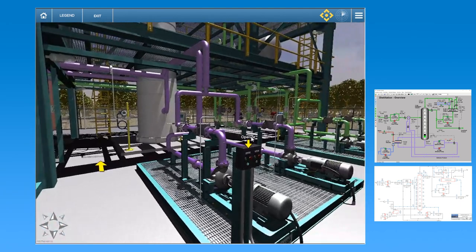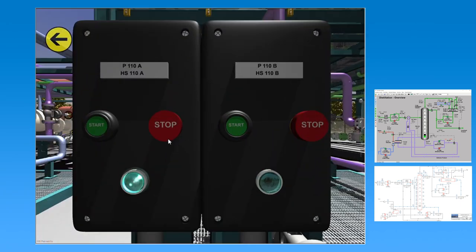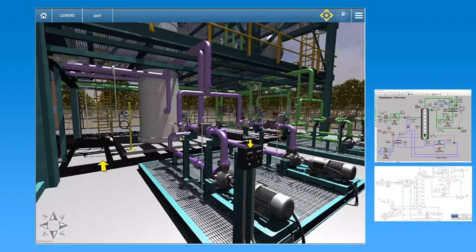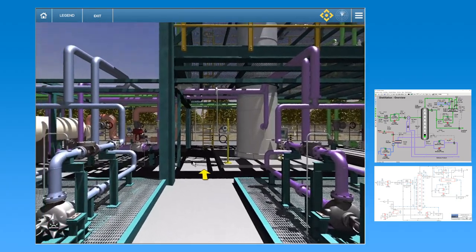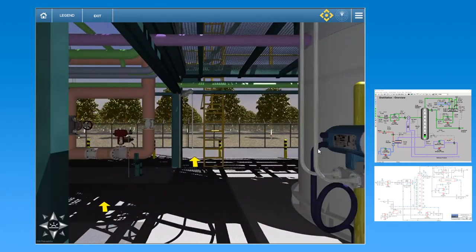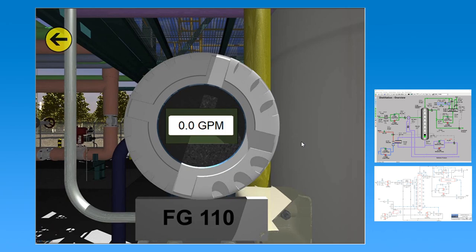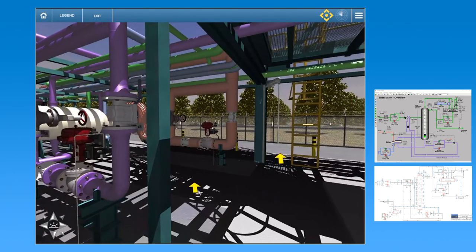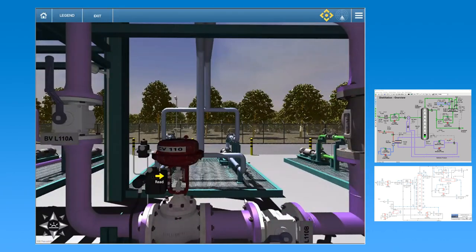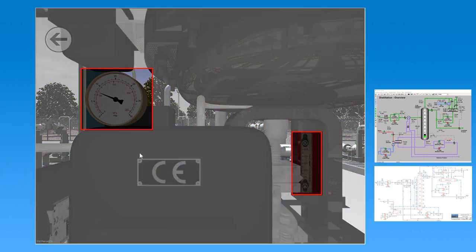The console operator decides to bring in the help of the field operator to verify readings and help with further troubleshooting. The field operator confirms various readings that rule out some of the options mentioned earlier. While examining the control valve, the operator notices that although the pressure indicator for the pneumatic actuator shows pressure, the travel indicator on the stem is at zero percent.